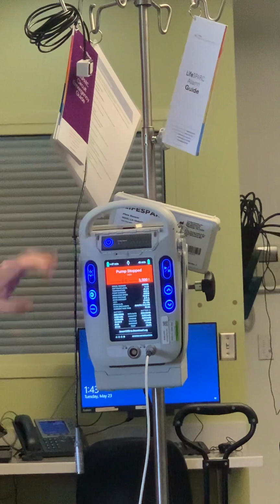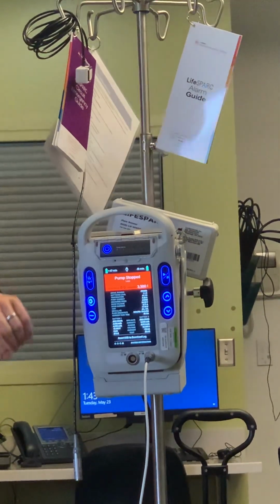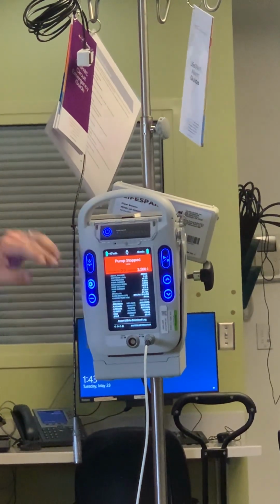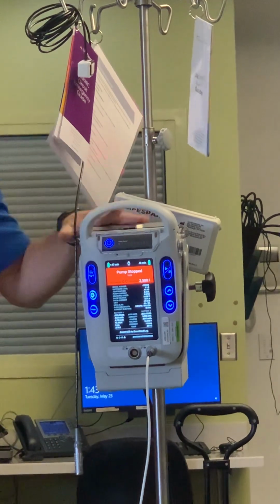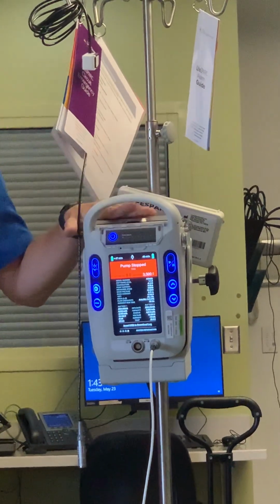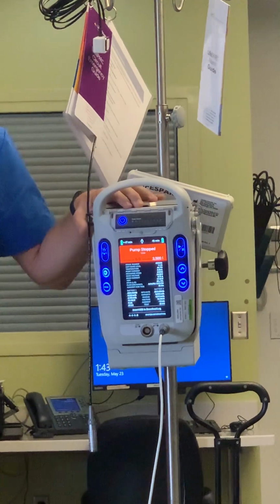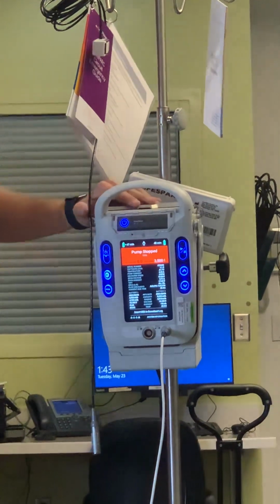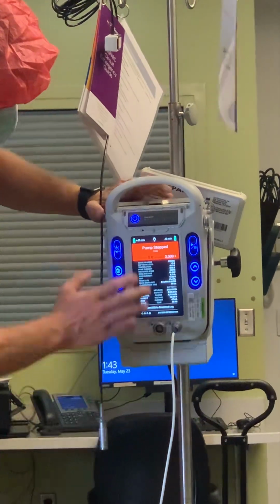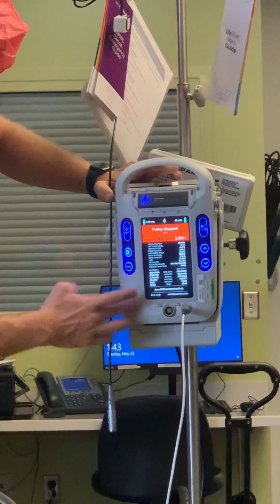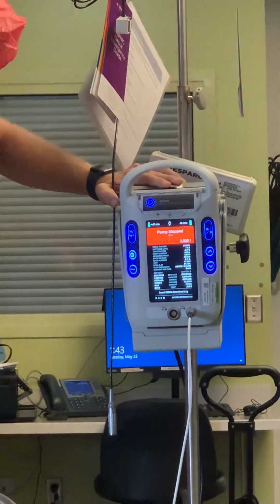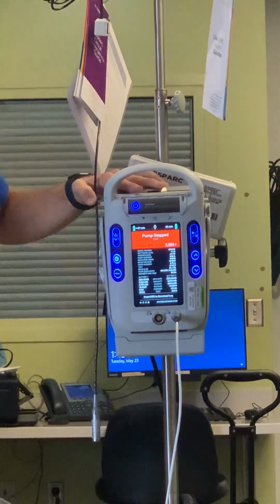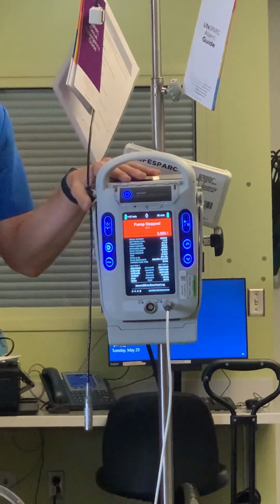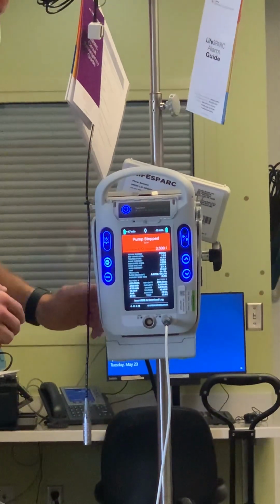And then the 4th screen is more just settings, and it's just telling you what's going on with the controller. This does not link to any alarm, so you're not going to be able to hook this up and send any information to Epic or any of your charting systems. There are 2 lithium-ion batteries, so that will tell you what's going on here. It will tell you the pump current, temperature, and that is in relation to the system, not necessarily the patient or the circuit.